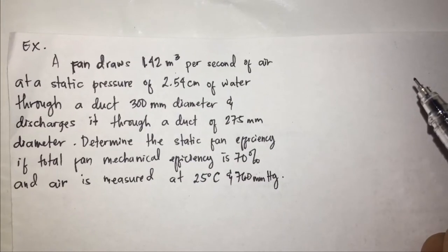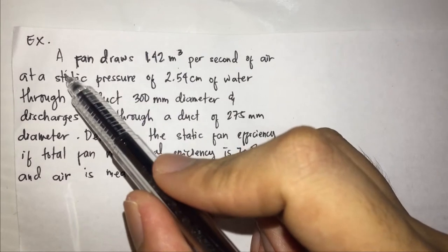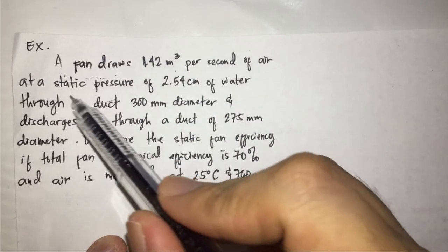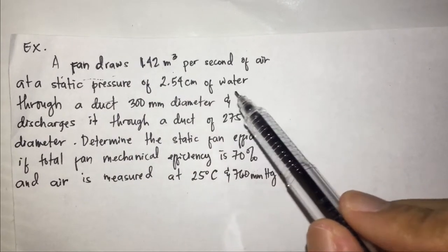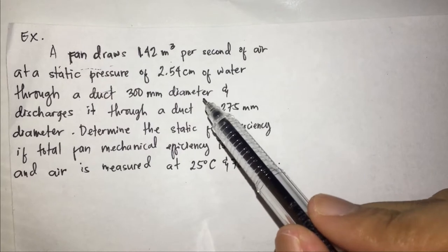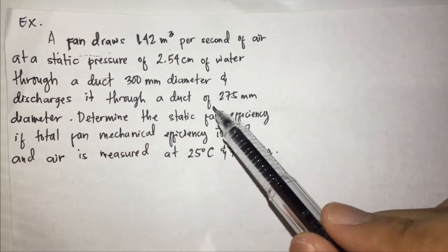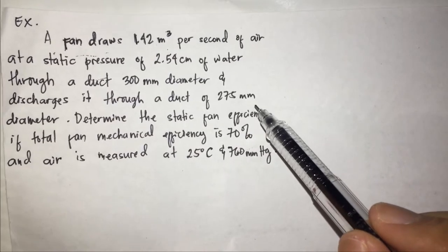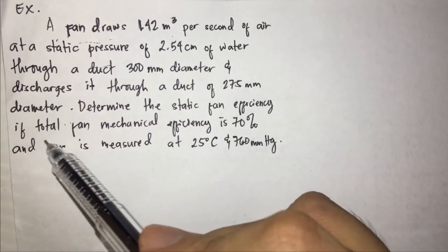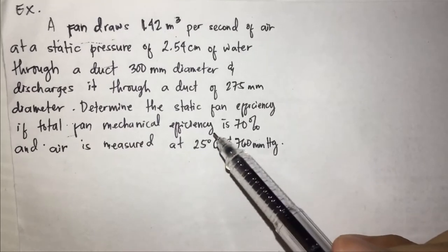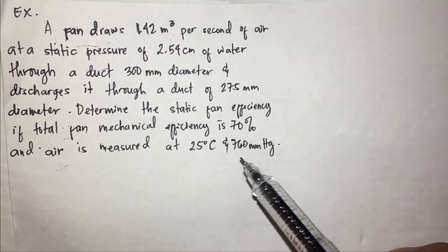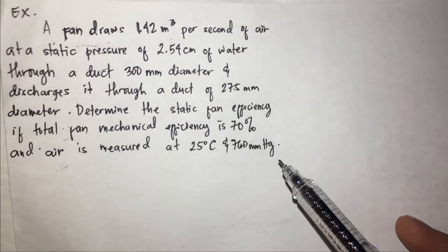Example of a fan problem. A fan draws 1.42 cubic meters per second of air at a static pressure of 2.54 cm of water, through a duct 300 mm diameter and discharges it through a duct of 275 mm diameter. Determine the static fan efficiency if total fan mechanical efficiency is 70% and air is measured at 25 degrees Celsius and 760 mmHg.